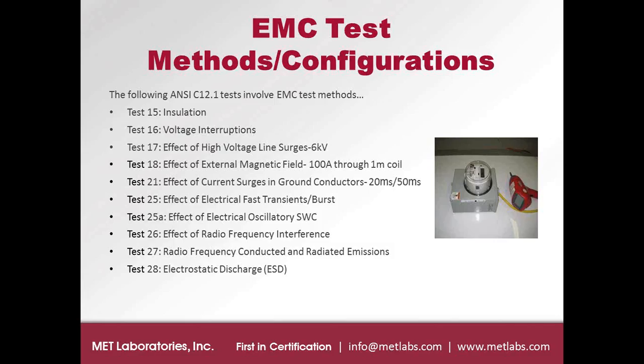Most of the other tests are very similar to the other IEC standards. The only difference is the surge test, test number 17, which is required at an amplitude of 6,000 volts. Normally, most equipment manufacturers are required to perform testing at 1 kilovolt, 2 kilovolts, sometimes a max of 4 kilovolts. But here we are required to perform up to 6 kilovolts, and most importantly, the impedance is 2 ohms, making the current combination 3,000 amps or 3 kiloamps.